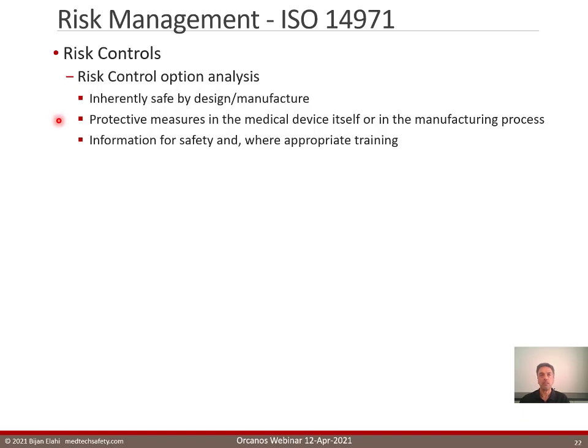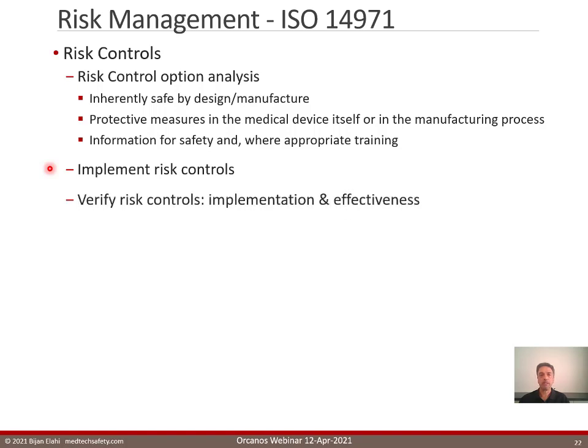If you're unable to do that, the next best thing is to put protective measures in the medical device itself or in the manufacturing process to prevent hazards from causing harm. And if that's not possible either, then the next best thing that you can do is to provide information for safety and, where appropriate, training, so people know how to use your device and be safe with it. So now that we have found some things to do to reduce risk, we implement those risk controls. But just implementing risk control doesn't mean for sure that risk is controlled and reduced. So now we have to verify those risk controls.